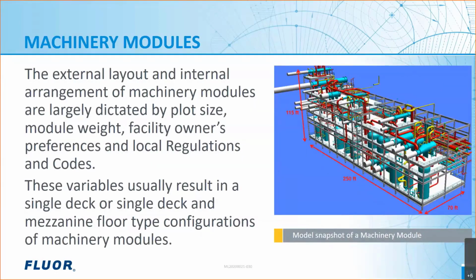The factors mentioned on this slide reflect a distinctive characteristic of machinery modules. It is the arrangement of the equipment string. Small modules have a single deck, and some other modules include a single deck and a mezzanine floor for the auxiliary equipment. Depending on the specific layout, one machinery string may be installed on a dedicated module, or two strings in the same service may be installed in longitudinal or transverse direction on the module floor. For modules that do not have a roof, air-cooled heat exchangers for lube oil may be integrated with module and mounted on top.